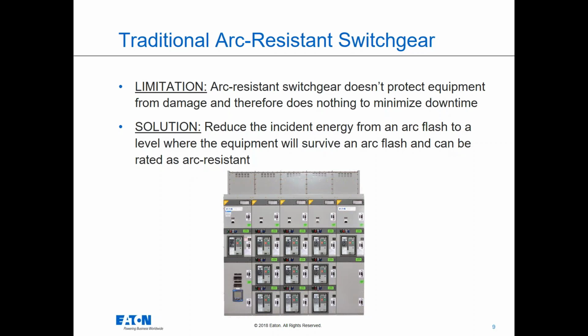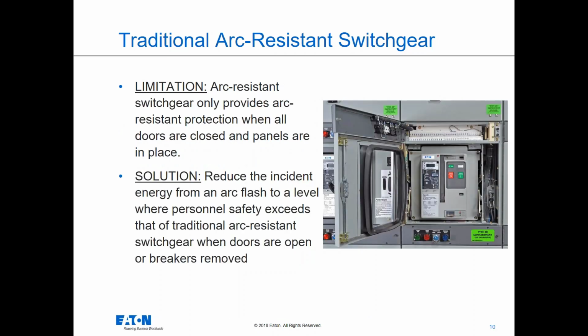You also generally can't configure the equipment the same way you would configure traditional switchgear. So there are some limitations in things like breaker placement and how you can arrange the components within the gear to satisfy the lineup. Those things come with limitations. With arc resistant switchgear, there are other things that do limit you.